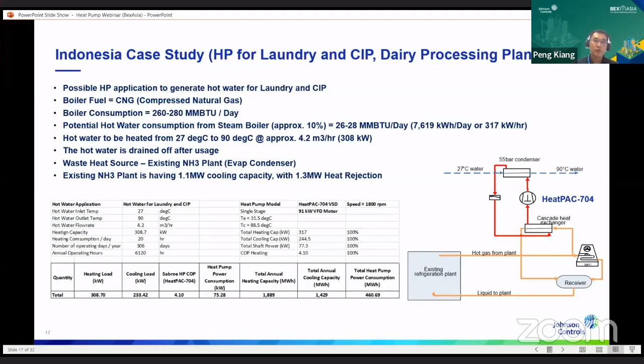So just bear with me a bit for the small print. What we have here is actually a comparison between boiler fuel consumption and the heat pump and electrical consumption to do the same amount of heating at the same time. So from the characteristic of the fuel, which in this case is methane natural gas, compressed natural gas, and the electricity bill that we can build out of this particular location in Indonesia, for example, we can actually do a parallel cost study between the two types of fuel consumption.